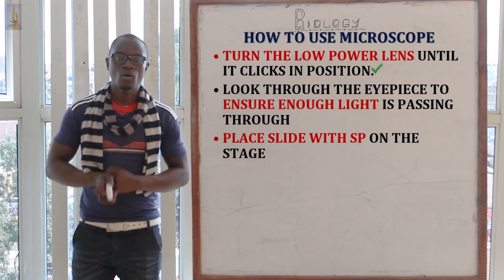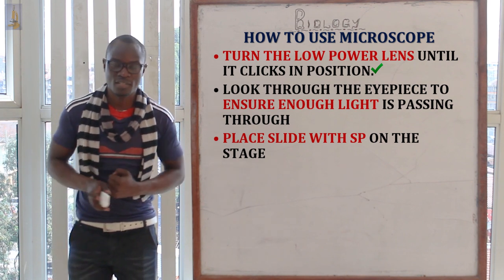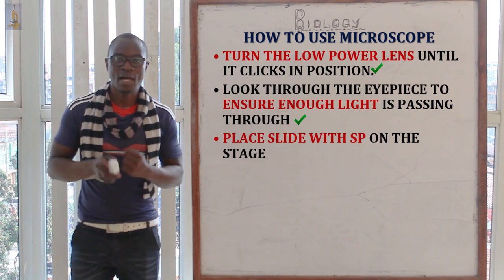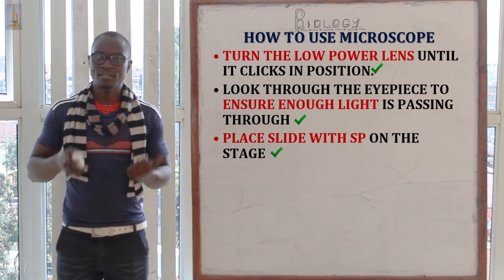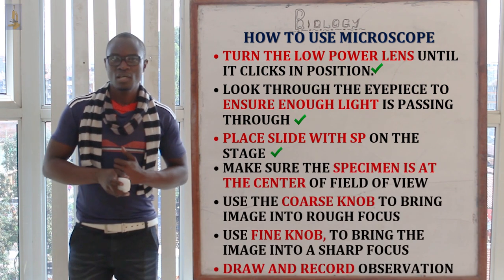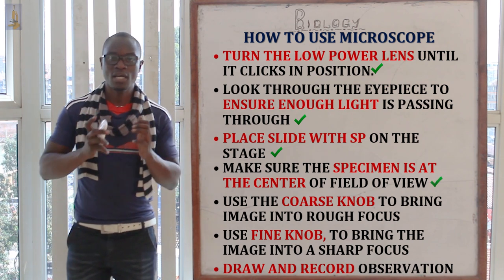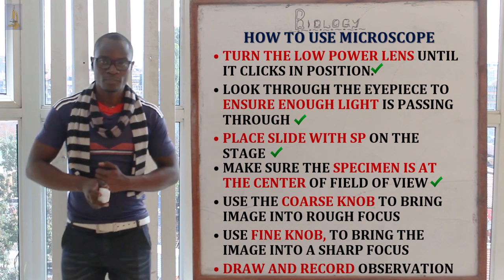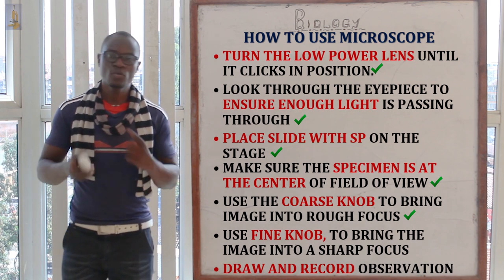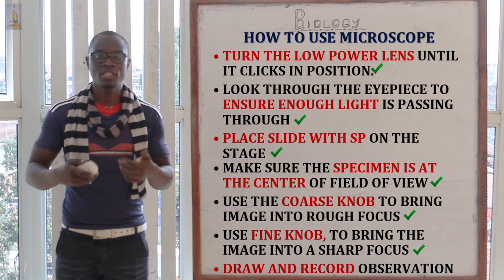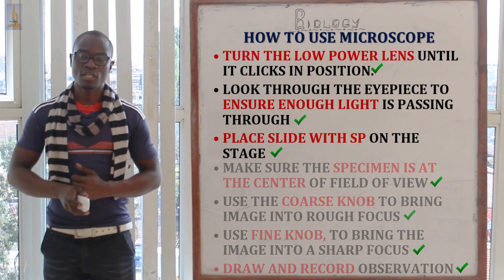To use the microscope: first, turn the low-power objective lens until it clicks into position. Then look through the eyepiece to ensure enough light is passing through. Place the slide containing the specimen on the stage and ensure the specimen is at the center of the field of view. Use the coarse adjustment knob to bring the image into rough focus, then use the fine adjustment knob to bring it into sharp focus. Finally, draw and record your observations.